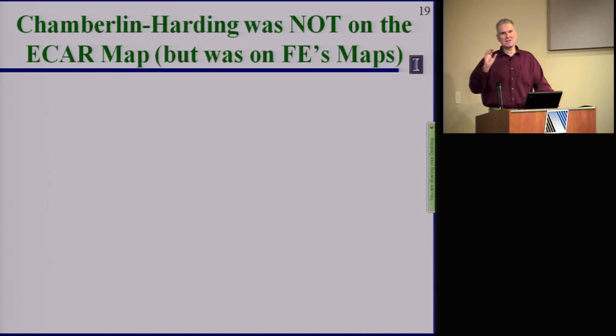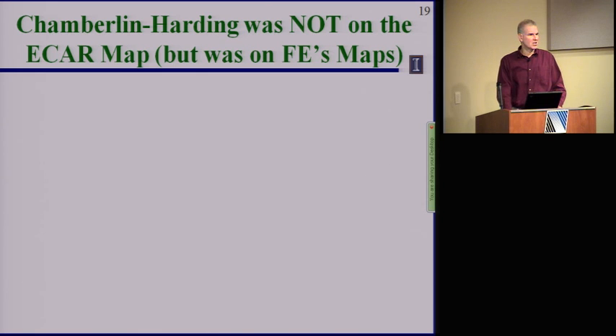And it did not come in saying that this line tripped. What it came in as was 4 alarms talking about 4 breakers opening, and that's just how alarms come in. So a lot of work has been done since then on alarm log prioritization so that people don't miss this anymore. But they missed it.